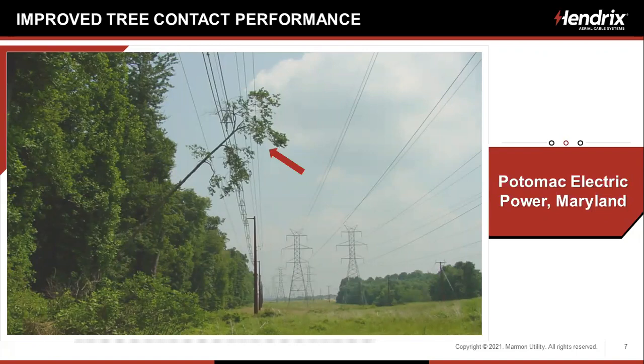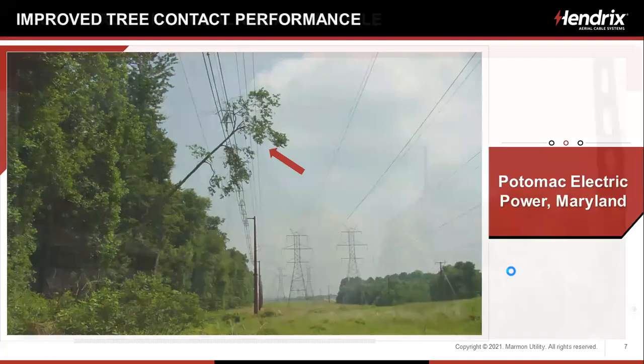Okay, I've got a couple of slides thrown in here just to show you some of the benefits. This is a system we have down at Pepco in Maryland where a tree fell on the 69 kV line. They have helicopter patrols every 6 months. This was found by a helicopter patrol. There was no outage. They went out and removed the tree, and the line survived. If this had been bare wire, everything would have been on the ground: that 69 kV line, as well as the 15 to 25 kV underbuild below it.